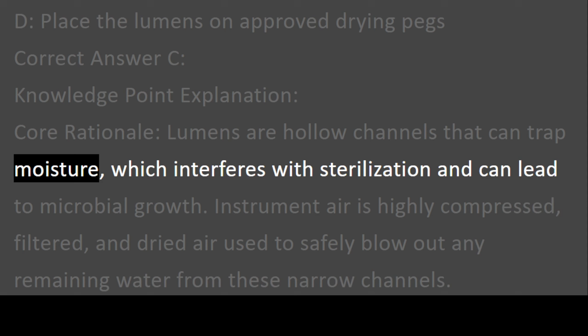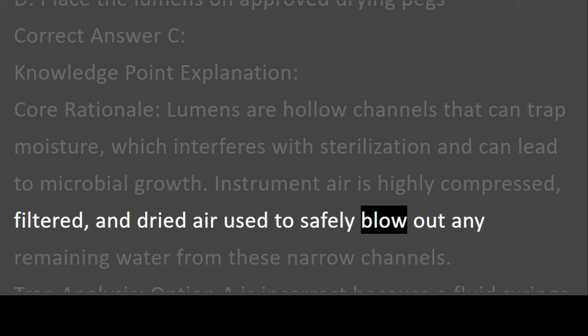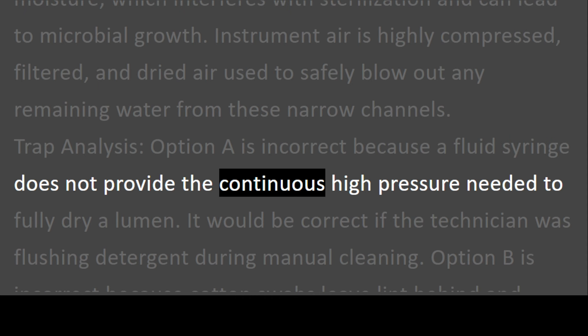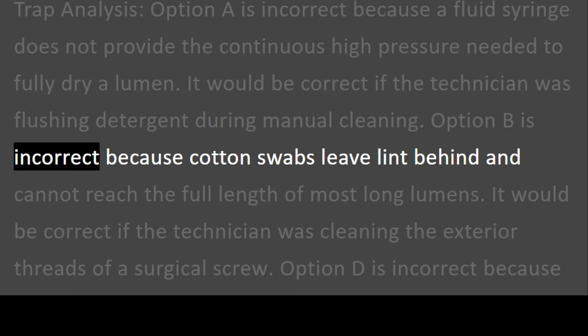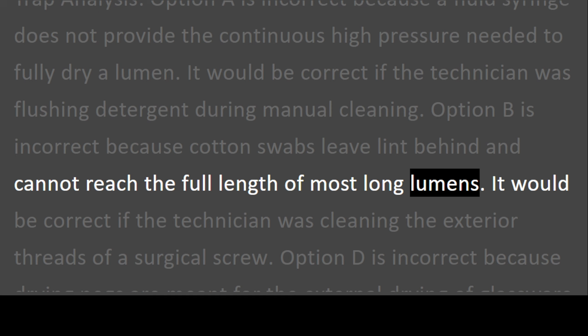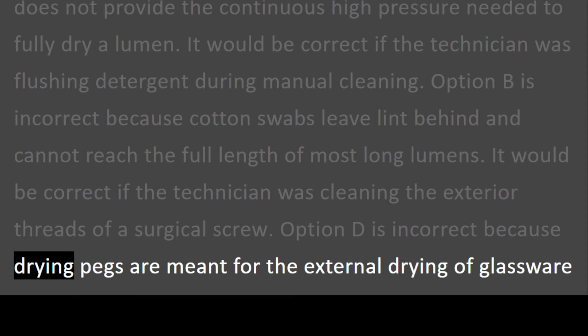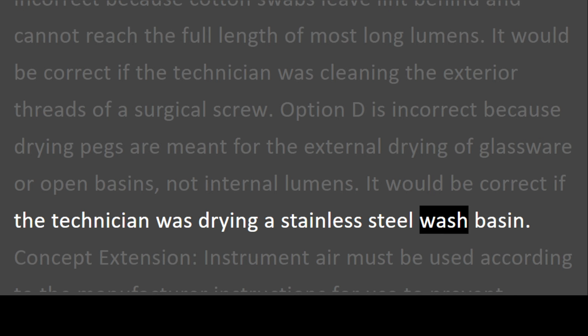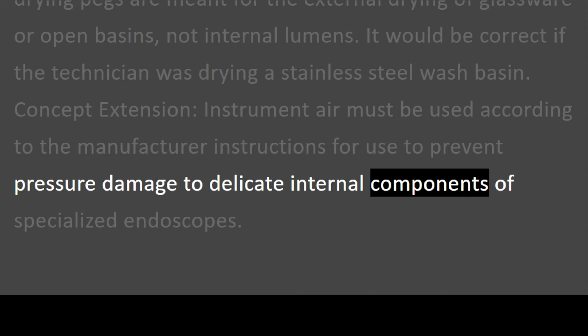Core rationale: lumens are hollow channels that can trap moisture, which interferes with sterilization and can lead to microbial growth. Instrument air is highly compressed, filtered, and dried air used to safely blow out any remaining water from these narrow channels. Trap analysis: option A is incorrect because a fluid syringe does not provide the continuous high pressure needed to fully dry a lumen. It would be correct if the technician was flushing detergent during manual cleaning. Option B is incorrect because cotton swabs leave lint behind and cannot reach the full length of most long lumens. It would be correct if the technician was cleaning the exterior threads of a surgical screw. Option D is incorrect because drying pegs are meant for the external drying of glassware or open basins, not internal lumens. It would be correct if the technician was drying a stainless steel wash basin. Concept extension: instrument air must be used according to the manufacturer instructions for use to prevent pressure damage to delicate internal components of specialized endoscopes.